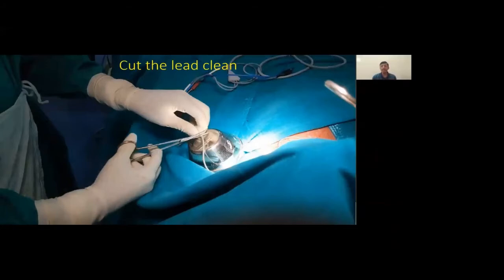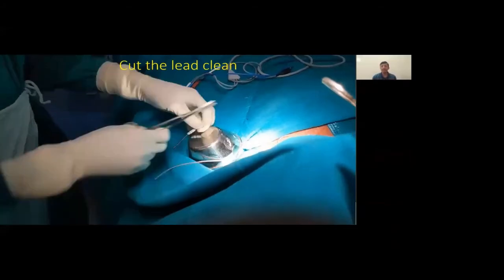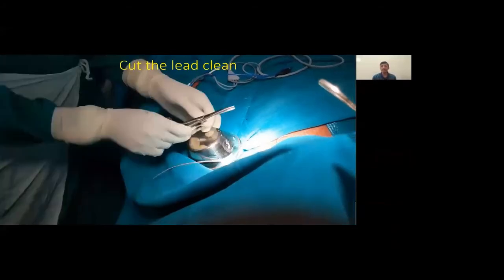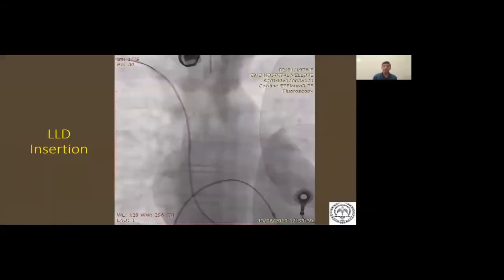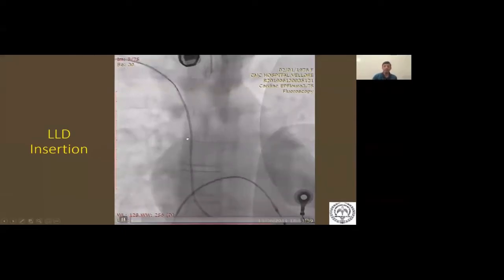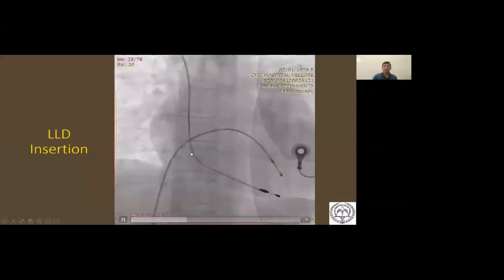So that's a clean cut rather than a jagged cut, because if you have a jagged cut, then it's hard to send your lead locking device through the lumen. Once that is done, then you send in the lead locking device. And as you can see here from this cartoon, you can see the lead locking device over there. The lead locking device needs to be sent so that it tracks all the way down to the very tip of the lead. So you can see here the lead locking device being sent.